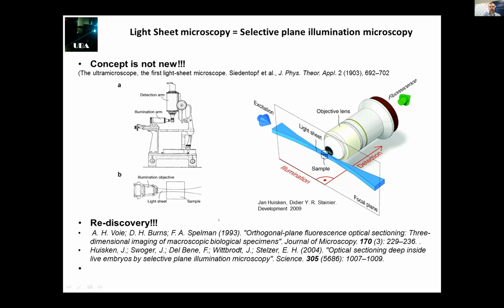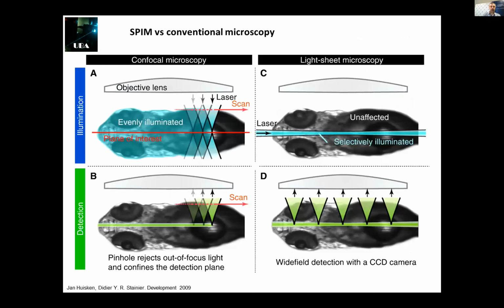The reason is what Nick mentioned yesterday: all the camera-based technology took a lot of time to develop. Until 1993, when people rediscovered this technology, and then through the work of Huisken and many others, it spread to different fields, in particular cell biology. So how does it work? Well, we can produce a light sheet using different strategies, which I will address in a minute, and then we can image with a second objective a full plane with confocal resolution, or with optical sectioning. And this has some advantages, which I will cover.